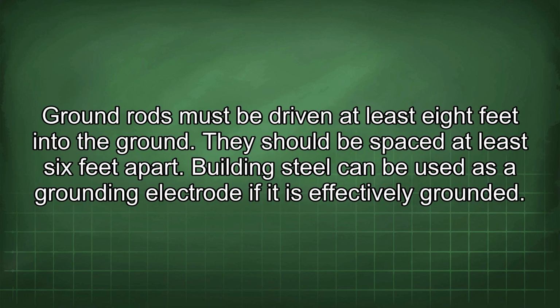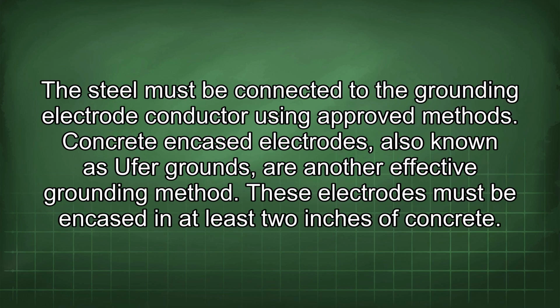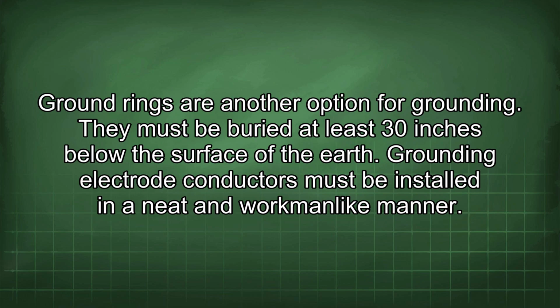Ground rods must be driven at least 8 feet into the ground. They should be spaced at least 6 feet apart. Building steel can be used as a grounding electrode if it is effectively grounded. The steel must be connected to the grounding electrode conductor using approved methods. Concrete encased electrodes, also known as Ufer grounds, are another effective grounding method. These electrodes must be encased in at least 2 inches of concrete. Ground rings are another option for grounding. They must be buried at least 30 inches below the surface of the earth.